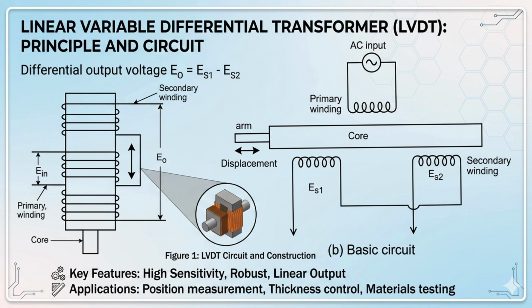The displacement to be measured is applied to the arm attached to the soft iron core. In order to overcome the problem of eddy current losses in the core, nickel iron alloy is used as the core material and is slotted longitudinally.